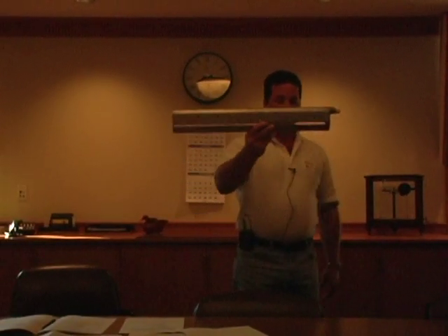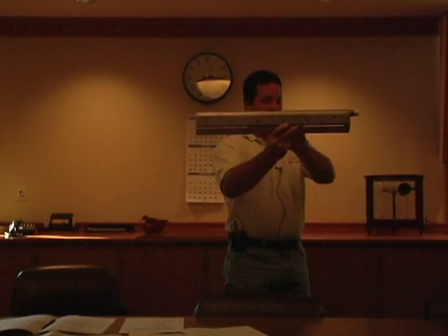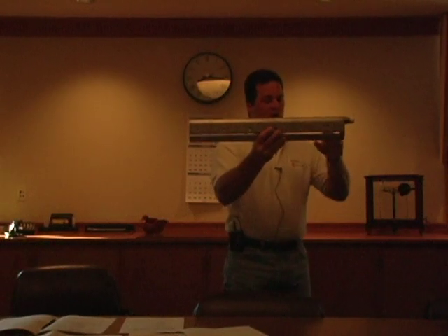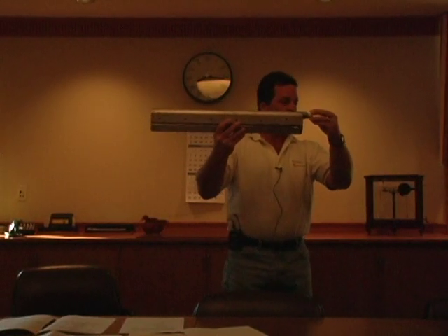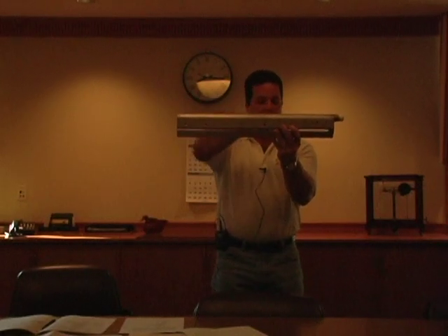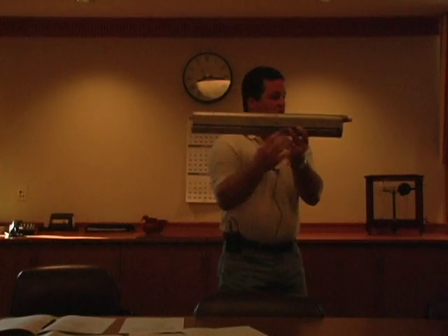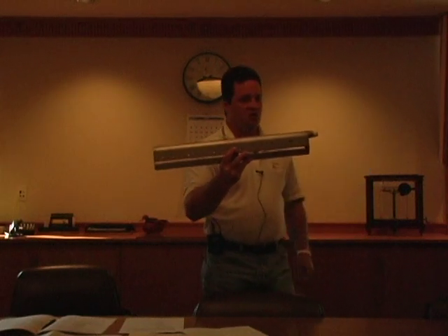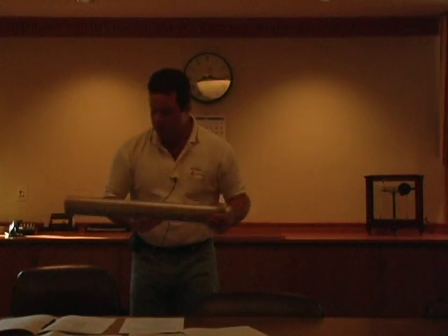The rotation, the actual way this diffuser is located in the tank is in this position. I've seen them sometimes installed differently. They have to be at this position right here. So what happens is the air will travel through this tube right here, which will be the orifice for the diffuser. Air will travel through the top of the diffuser and then come out the bottom, and the air will come out through both the channels and the holes themselves. This right here gives a nice rolling effect in, say, your channels and tanks, and you can get your suspended solids correctly. So that is the orientation of where this diffuser should be.